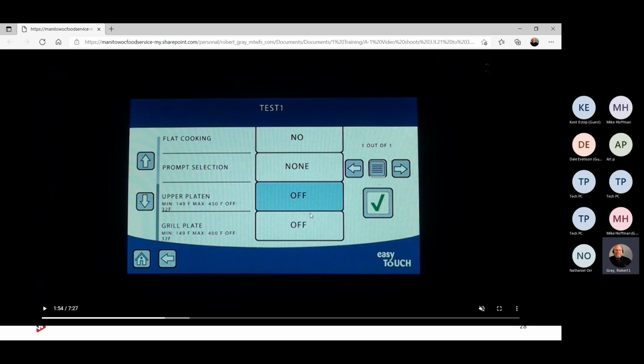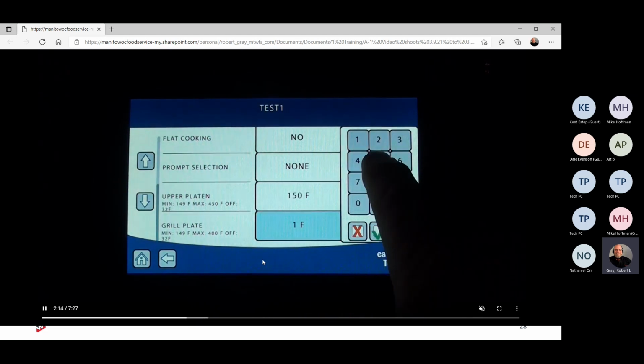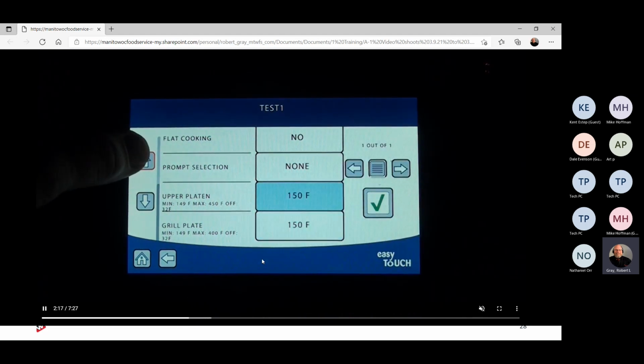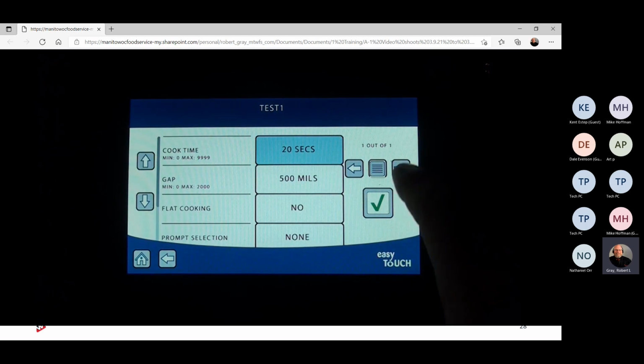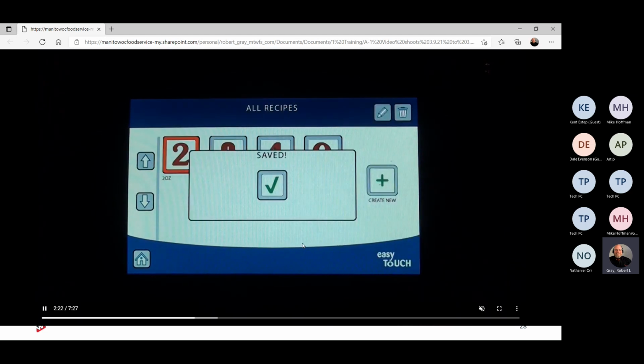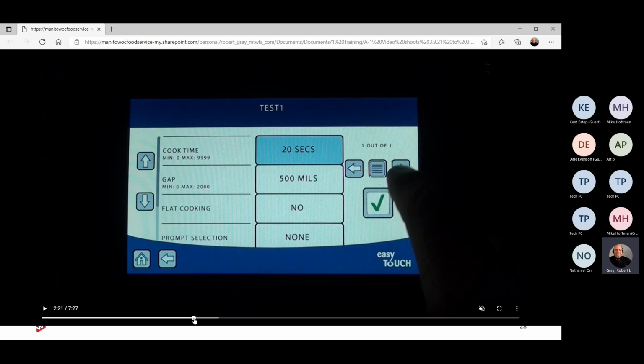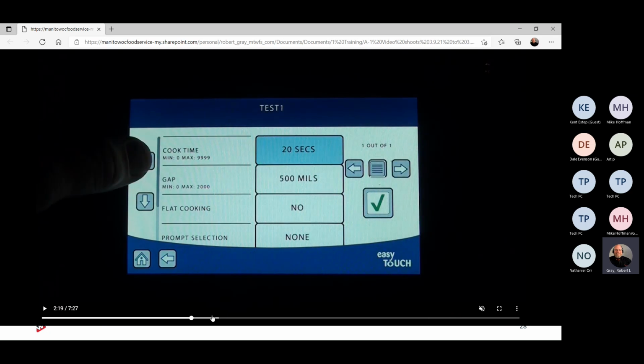So again, we're just going to simply click on that and highlight the button, and you'll see a keypad pop up. And you enter in the time. Again, because this is just creating a menu for training purposes, I just put 150. Now, let me back up there 1 second. And a little bit further. There we go. Now that all my cooking recipe is installed, with the exception, this is stage 1. So stage 1 might be 20 seconds. So I might have to add another stage.